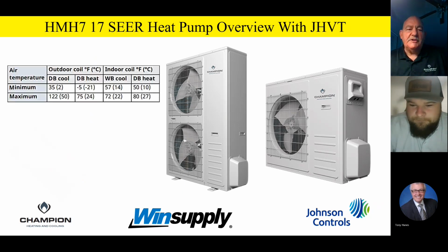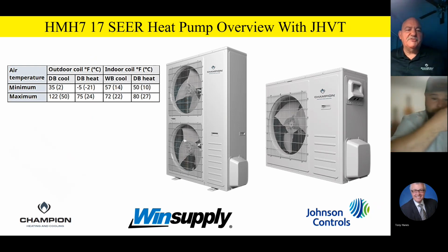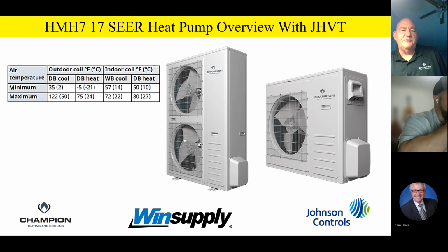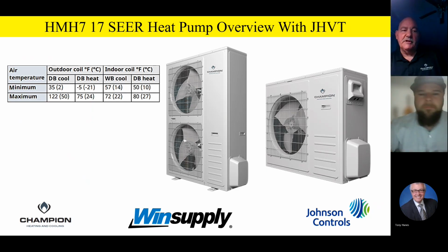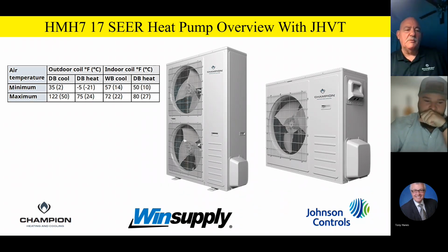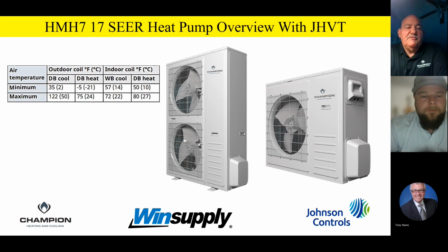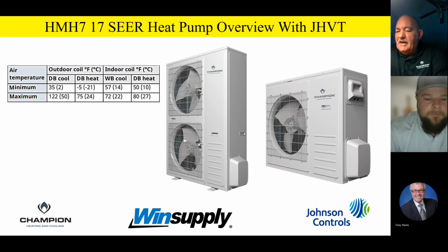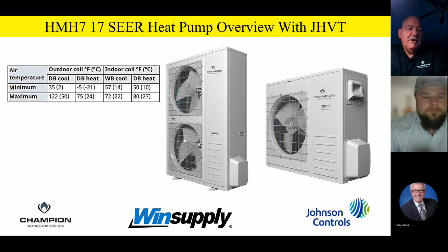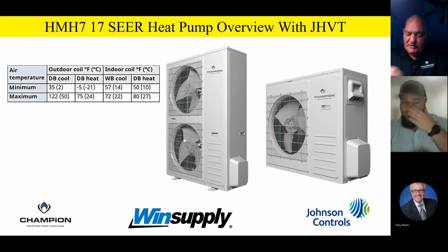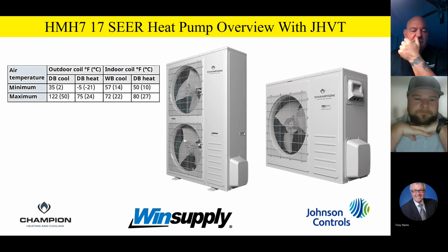In addition, I always like to kind of kick off our training a little bit with some minimum and maximum air temperatures. You'll see that on the slide right here. Minimum is 35 degrees cooling and -5 in the heating mode of operations, which is pretty remarkable for a unit right out of the box. And then your maximum outdoor temp is going to be 122 for cooling, and then 75 degrees for heating. Now, normally you wouldn't see people heating at 75 degrees, but it's nice to know the system does have that capability. If you've got a special situation, where the homeowner wants to heat the home inside, even when it's 75 degrees outside. So you have quite a broad range there on the HMH7 as far as capacities.